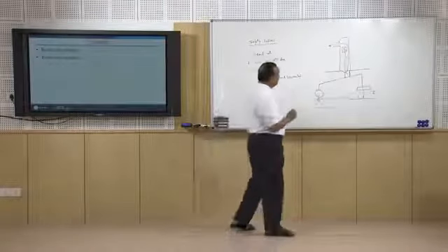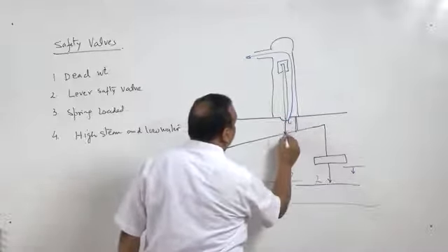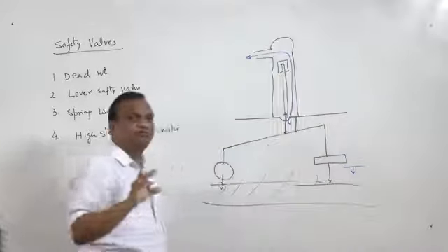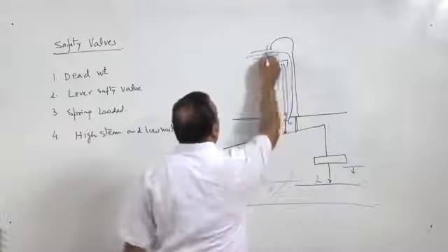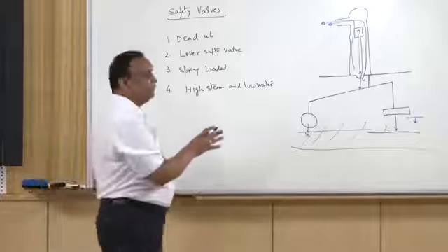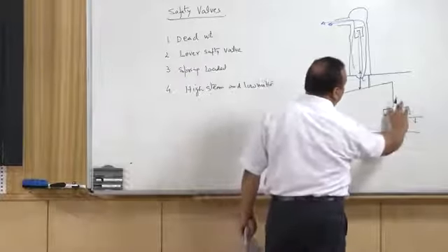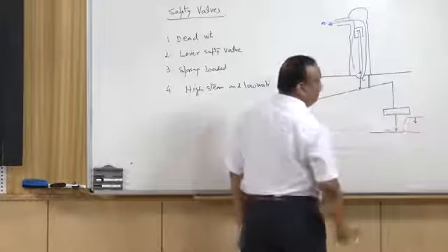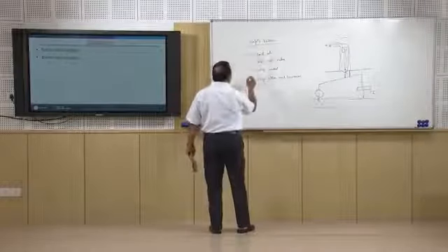Now in that case, this force will be exerted on this disc, this disc will open, and this arrangement is a sort of dead weight safety valve type of arrangement, and again the steam will vent off, but this sound will be different from the previous sound. So the operator will come to know this is the normal venting when the pressure of the steam is high, and the previous one was the sound of the venting steam when the water level was low in the boiler, right.